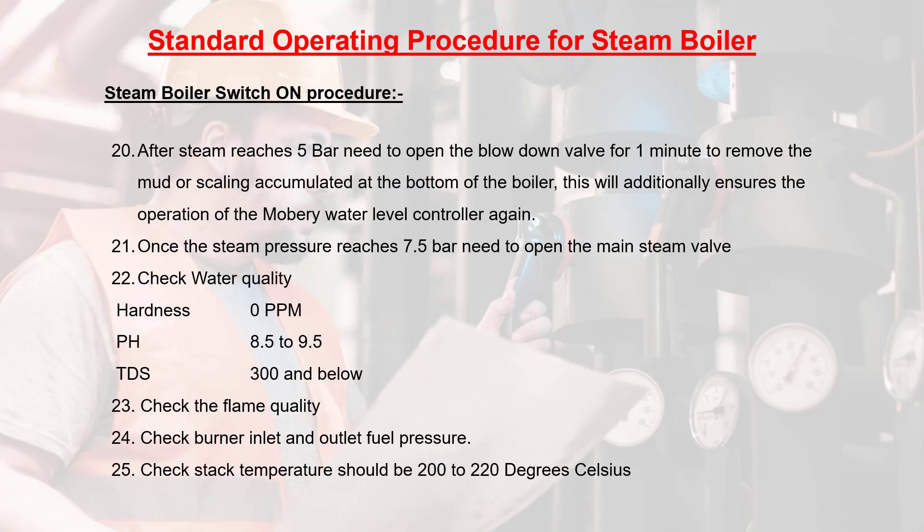Step 20: after steam reaches 5 bar, open the blowdown valve for 1 minute to remove mud or scaling accumulated at the bottom of the boiler. This will additionally ensure the operation of the Mobrey water level controller. Step 21: once the steam pressure reaches 7.5 bar, open the main steam valve.